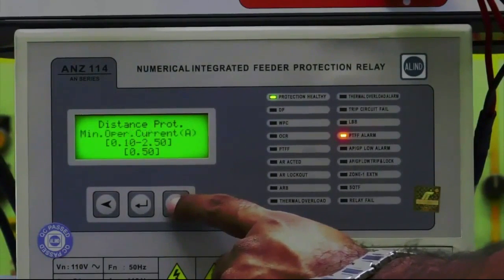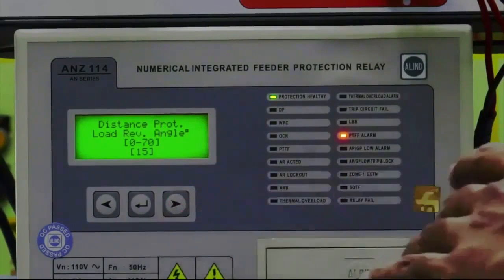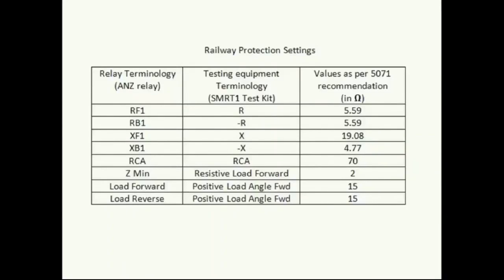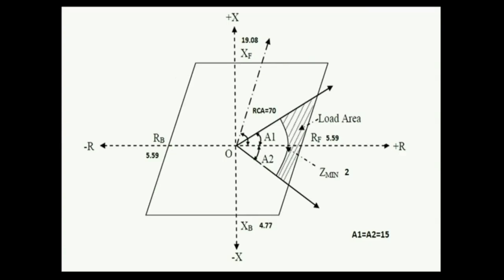RCA is 70, minimum operating current is 0.5 and line impedance is 0.22 ohms per kilometer. Z minimum is 2 ohms, load forward angle 15, load reverse angle 15. These values are in line with the characteristics defined in railway standard. So you can see the XF, RF, RB and XB values reflected in the drawing as per the relay. And the load area plus or minus 15 is actually the load encroachment angle with Zmin as 2 ohms.